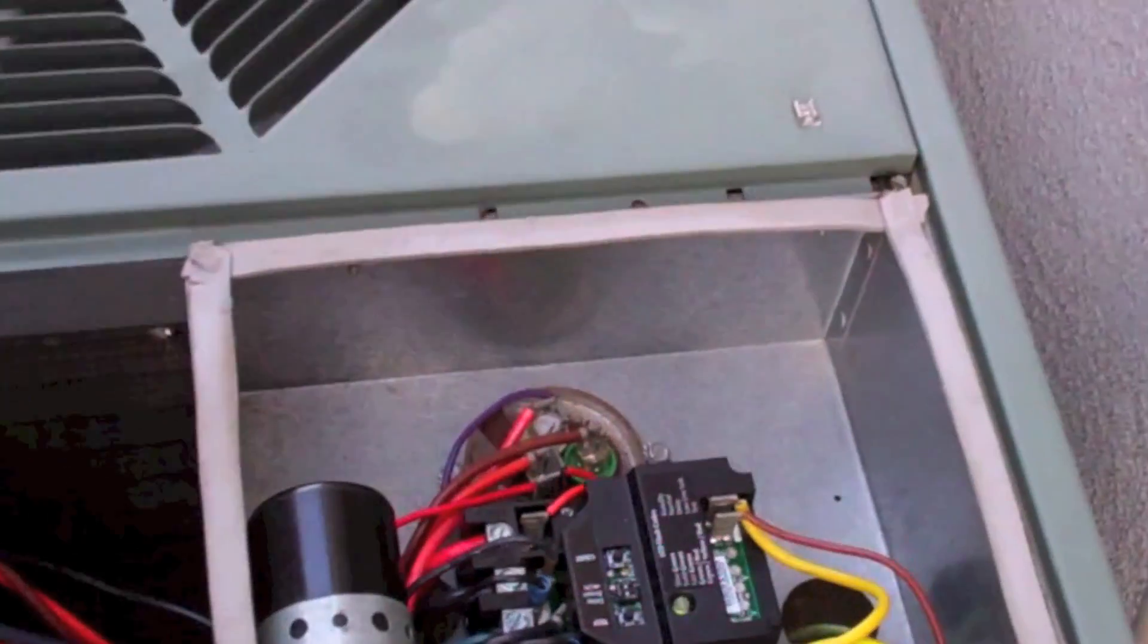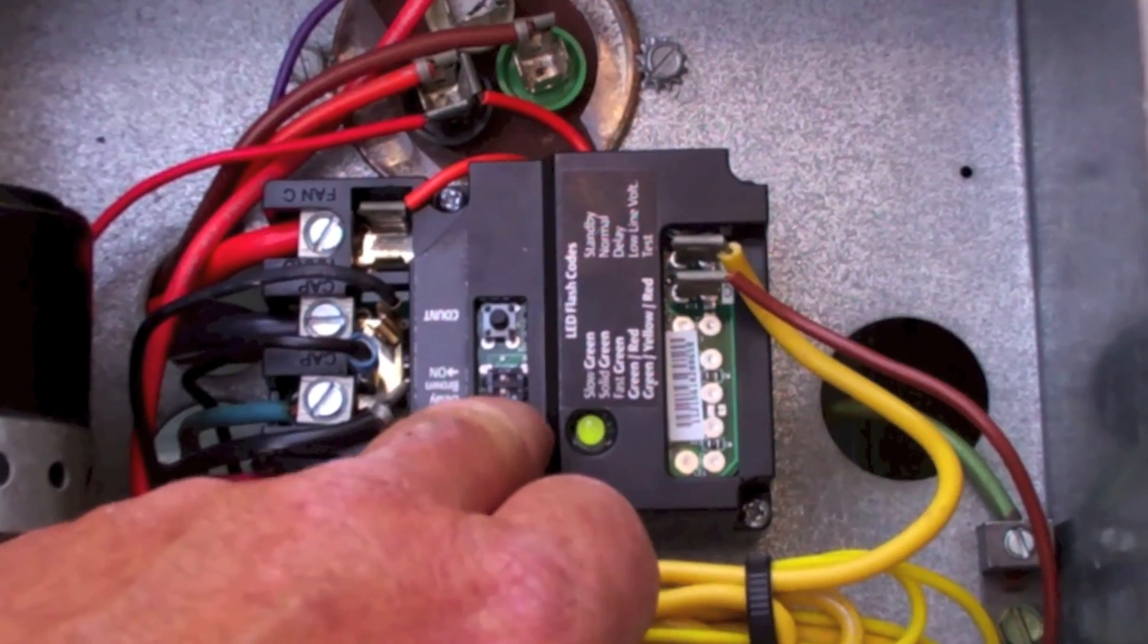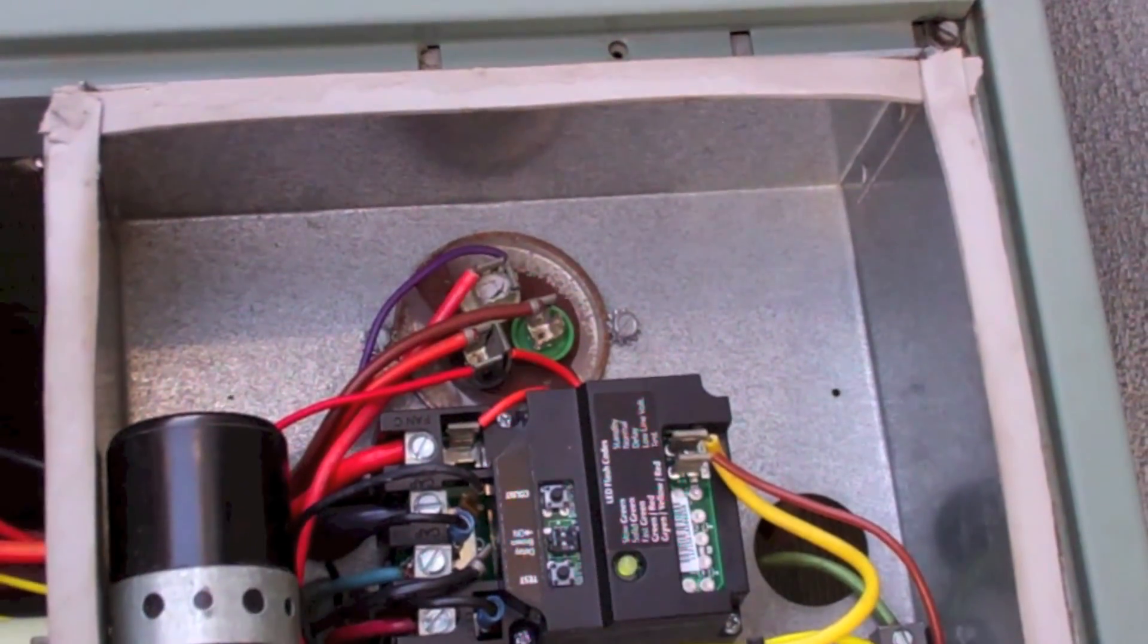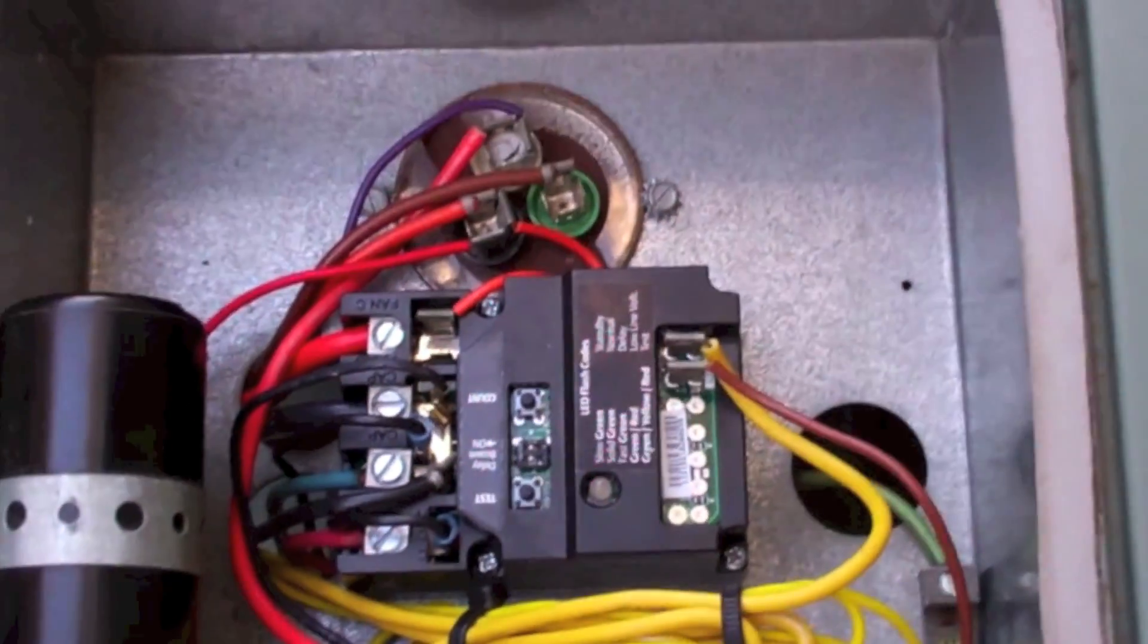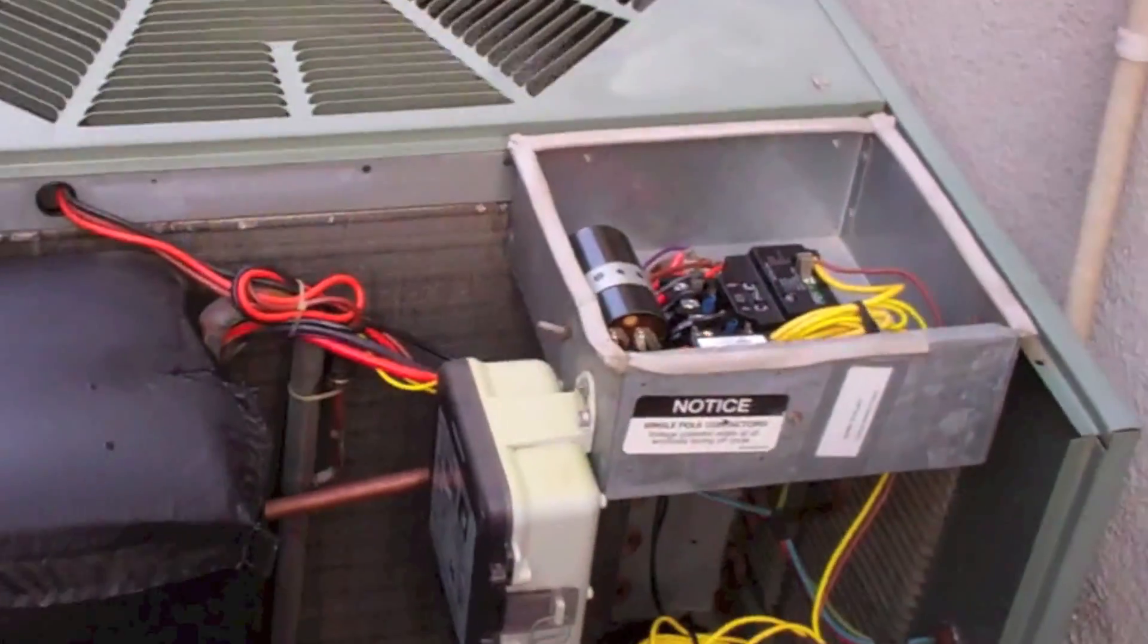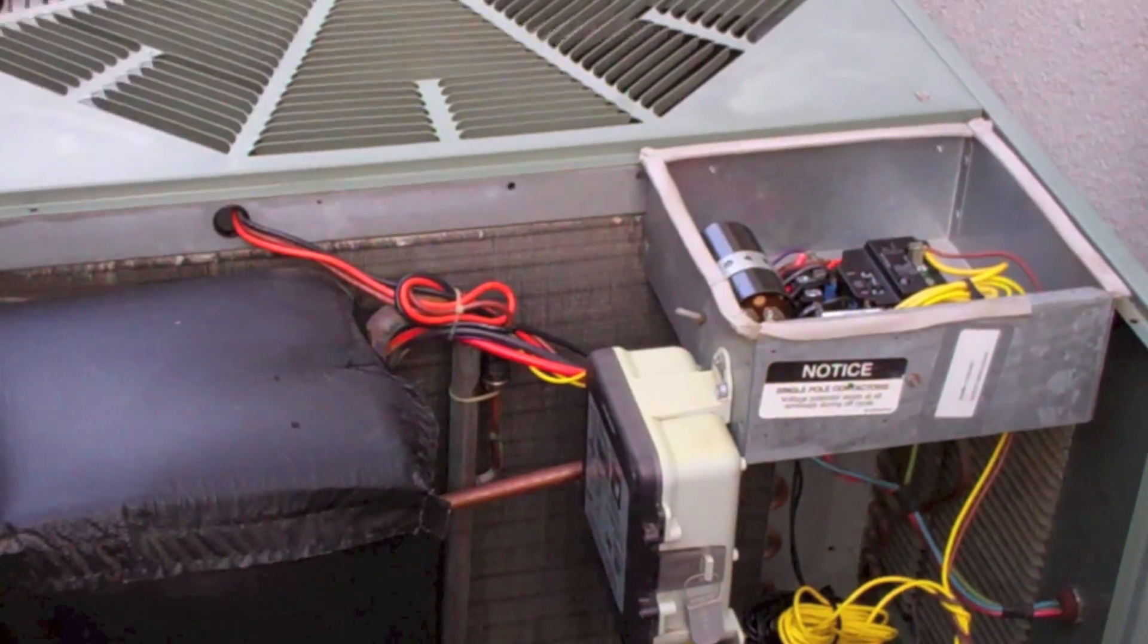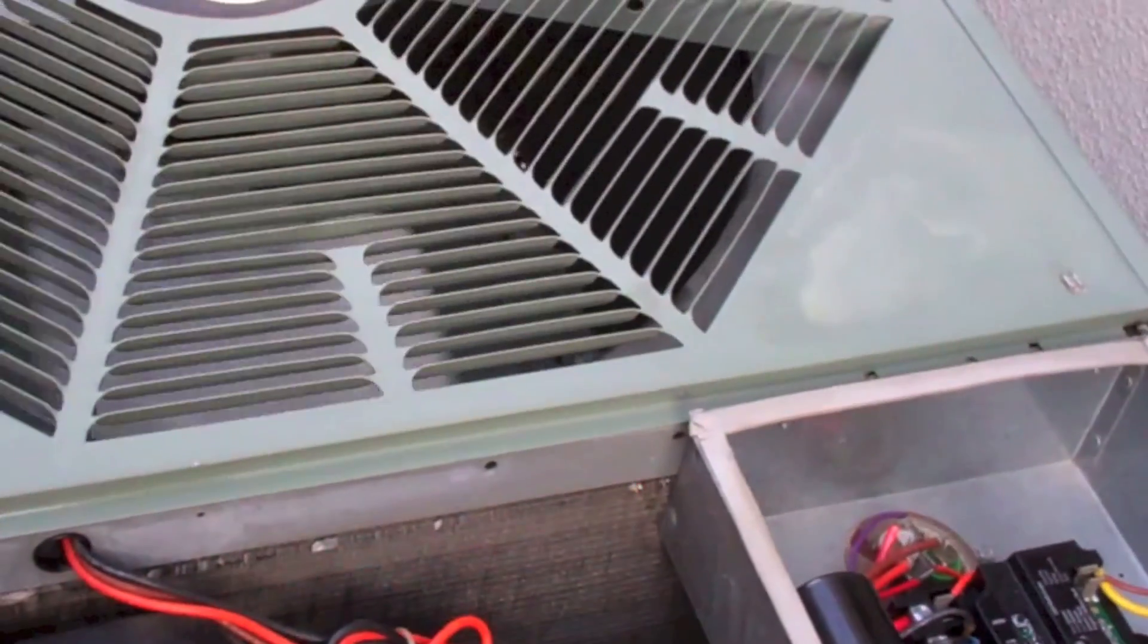I like it. Let me try it again. I like it because it's actually a little bit quieter - you don't hear the thumping of that contactor. So it's smooth starting. So I'm gonna go fire up the air and see how it works.